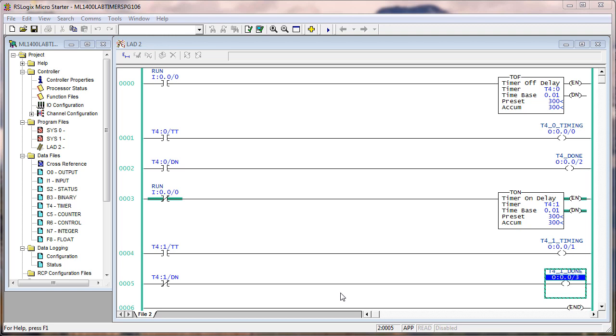In the upper logic, rung zero, you are enabling that TOF when input zero goes on. In rung three, you enable it when input zero goes off. So this firmly demonstrates that you can make a TON behave like a TOF because you're delaying the off instead of delaying the on.